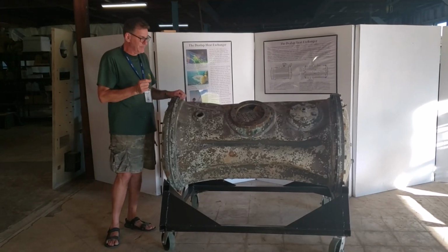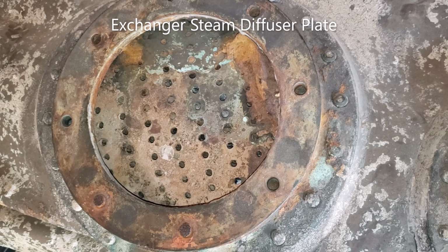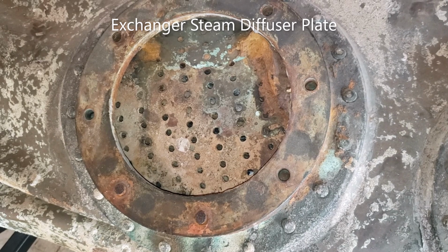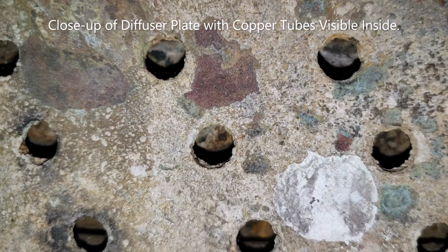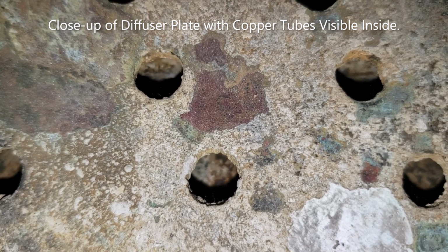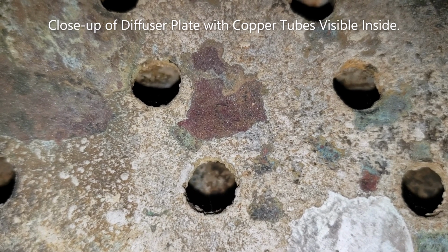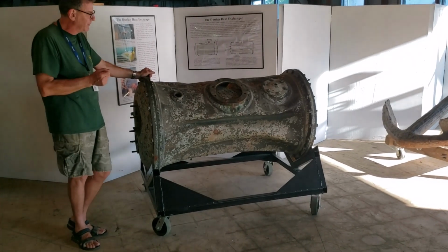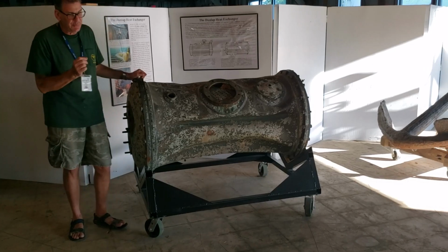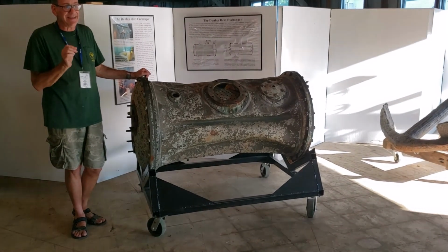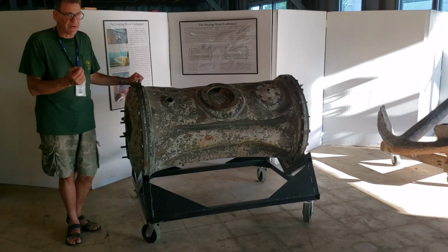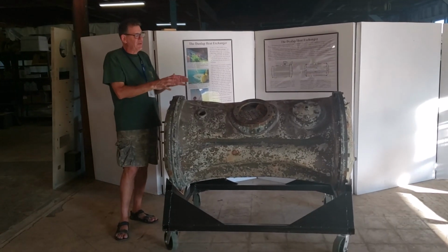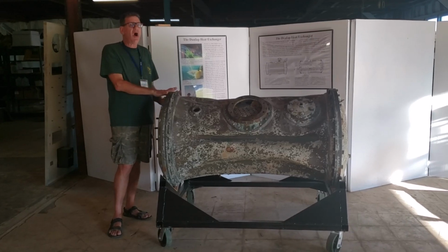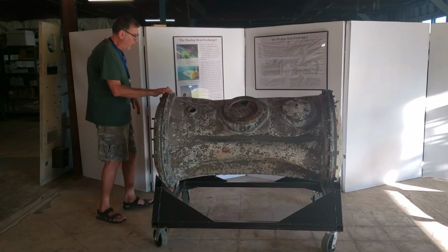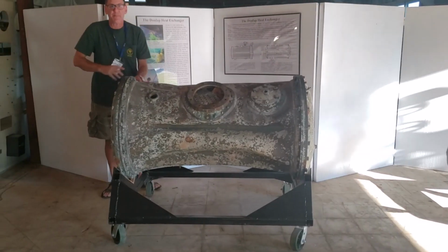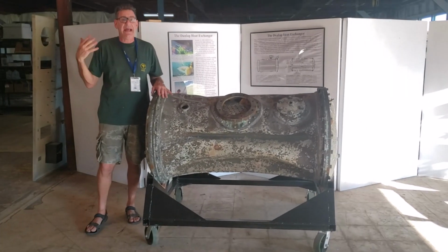Water is nearly incompressible. But there's airspace, gas space around those tubes. When the steam is surrounding all of those tubes, they resemble a cold drink on a hot day. It sweats. The tubes sweat water. That water sweats off these tubes at such a rate that in full operation, what's going on in here resembles a downpour. That water is collected, it's condensed steam, it's collected and comes out a port at the bottom, travels back into the boiler, is reheated and used again and again.